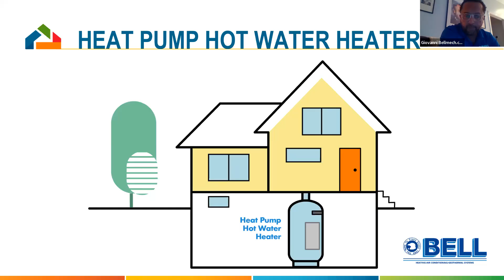So the heat pump hot water heater, and I saw a question before, I think somebody was asking if you can use one heat pump to give you both heat, AC and hot water. The answer is yes, only if you're doing a geothermal. But if you have an air source heat pump, you will need a separate source to give you hot water. The heat pump hot water heater is basically the same concept, same technology as the air source or ground source heat pumps. It is essentially using a heat pump sitting on top. If you notice the black portion of this water heater, that is basically the heat pump, and it's using electricity to transfer heat.